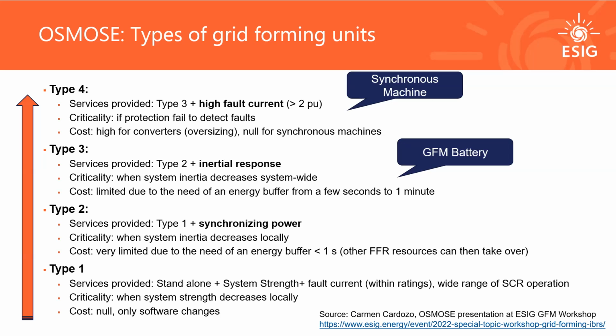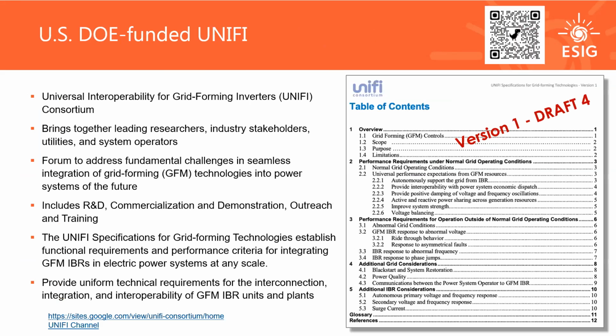Type 3 is type 2 plus adding inertial response. So this is when you're seeing global inertia decline at the system level. And then type 4 is when higher fault current level is needed for protection. And so this requires either oversizing of inverters, or maybe that's where synchronous machines are still really good to provide, because they can do fault currents way over the rating of the machine.